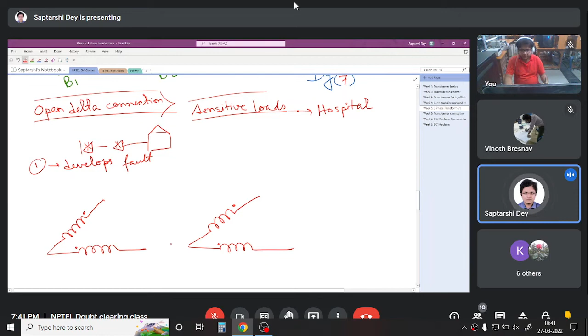As a result, in the hospital they will be told that this has happened to the transformer, and they have to immediately turn off all the unnecessary loads. Unnecessary loads means maybe the corridor illumination, the TV screens for the relatives of the patients, and such things. They turn these off so that the transformer in open delta formation is still capable of supplying the load at a reduced level. Obviously, the emergency load they can supply.